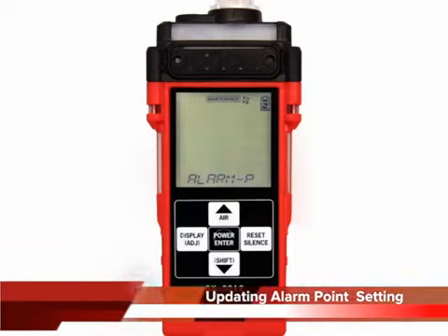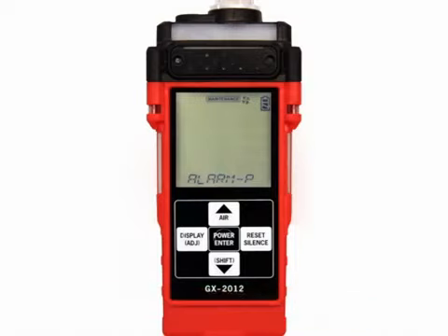The Alarm Points menu item allows you to update one or more of the following settings: warning, alarm, STEL, and TWA. For the combustible gas channel, it is not possible to adjust either the warning or alarm settings to be higher than 60% LEL. In addition, the warning setting cannot be adjusted higher than the alarm setting for all channels. It is not necessary to adjust every setting for every channel when you enter this menu item. All settings are shown here for example.